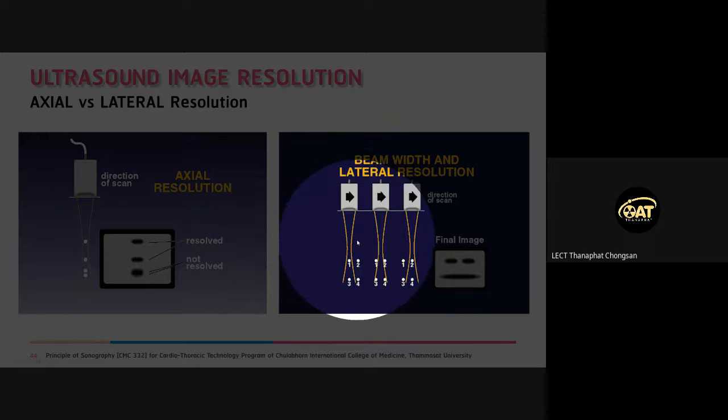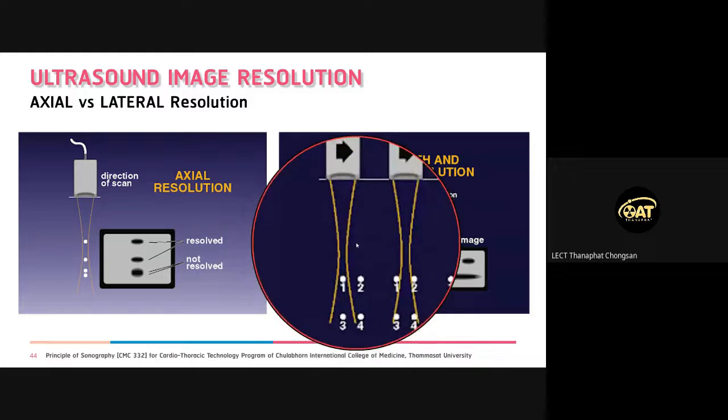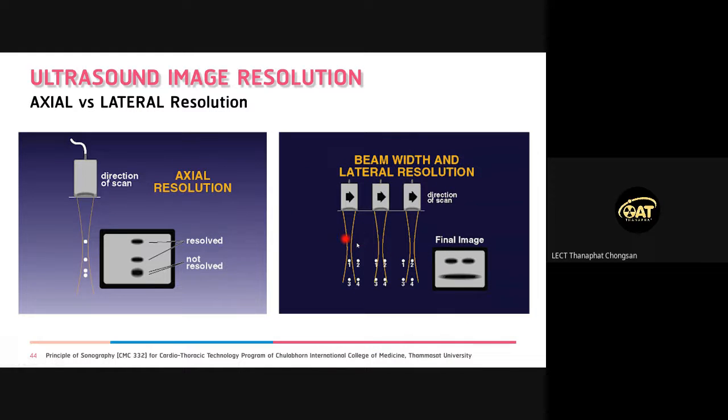This area is called focus depth. In Thai, this is the neck position here, the convex area. Sometimes we call it the focus area, the position that we call the focus position. This focus area is the base of lateral resolution, meaning the focus area in the middle is the position with the best lateral resolution.